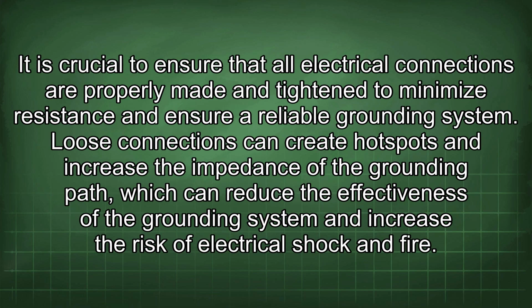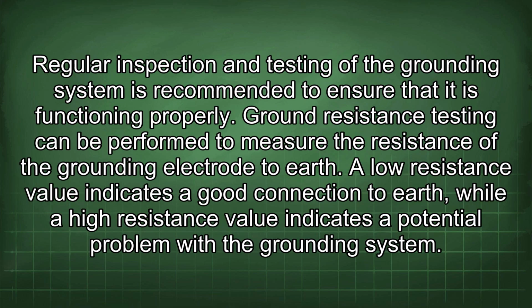It is crucial to ensure that all electrical connections are properly made and tightened to minimize resistance and ensure a reliable grounding system. Loose connections can create hotspots and increase the impedance of the grounding path, which can reduce the effectiveness of the grounding system and increase the risk of electrical shock and fire. Regular inspection and testing of the grounding system is recommended to ensure that it is functioning properly. Ground resistance testing can be performed to measure the resistance of the grounding electrode to earth.